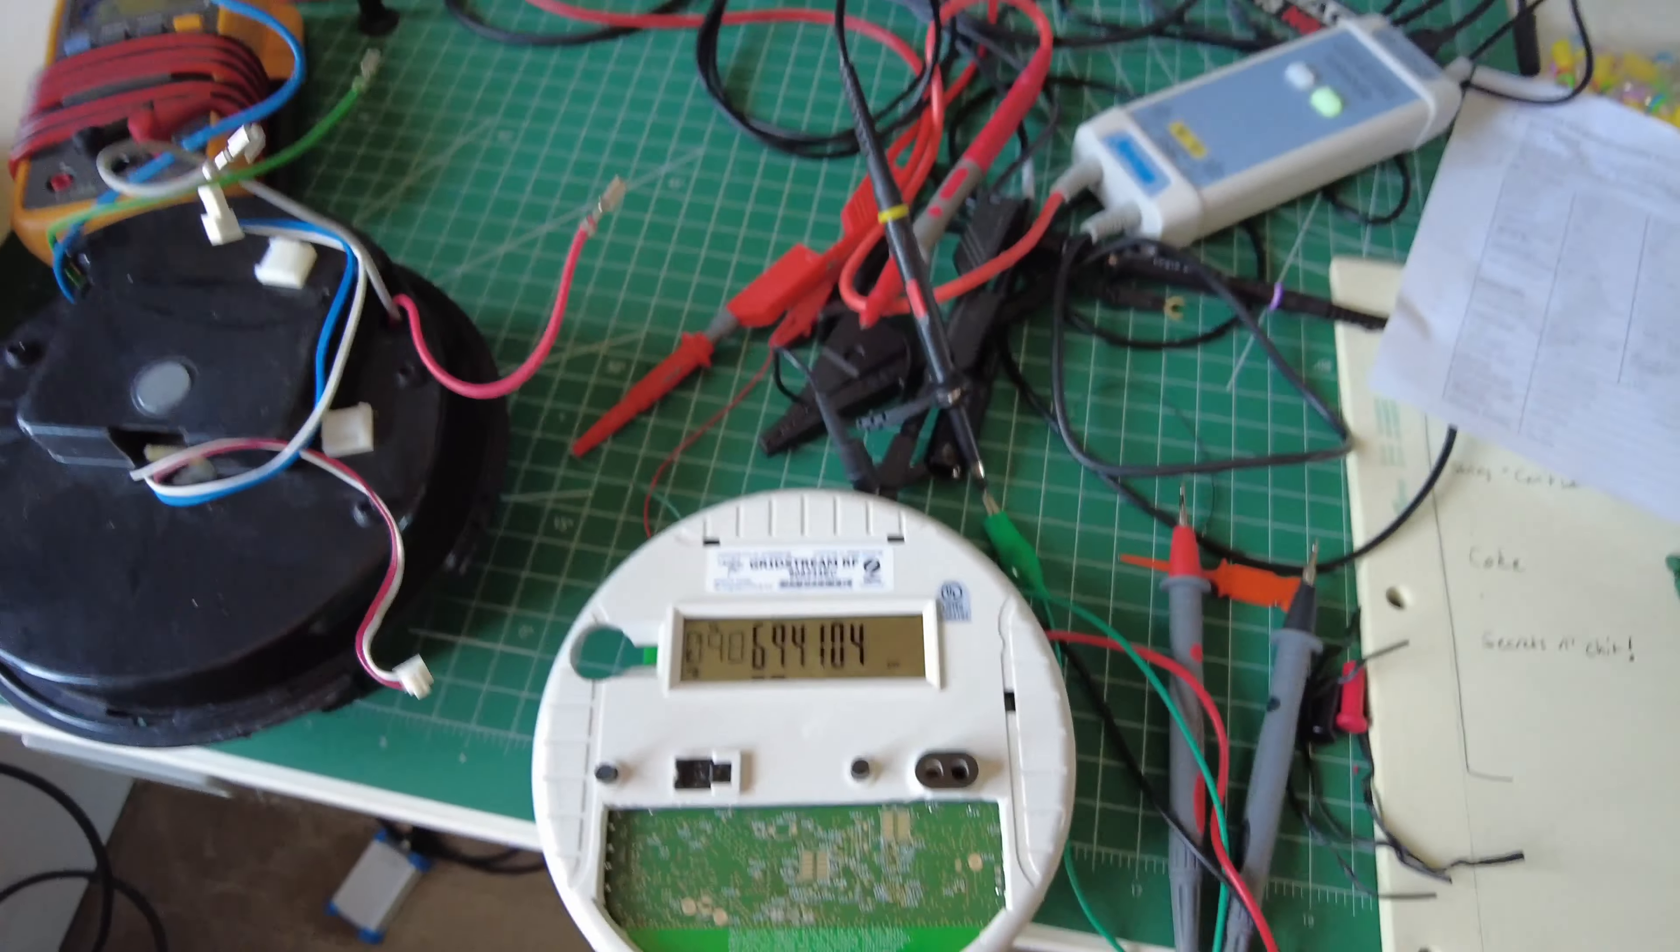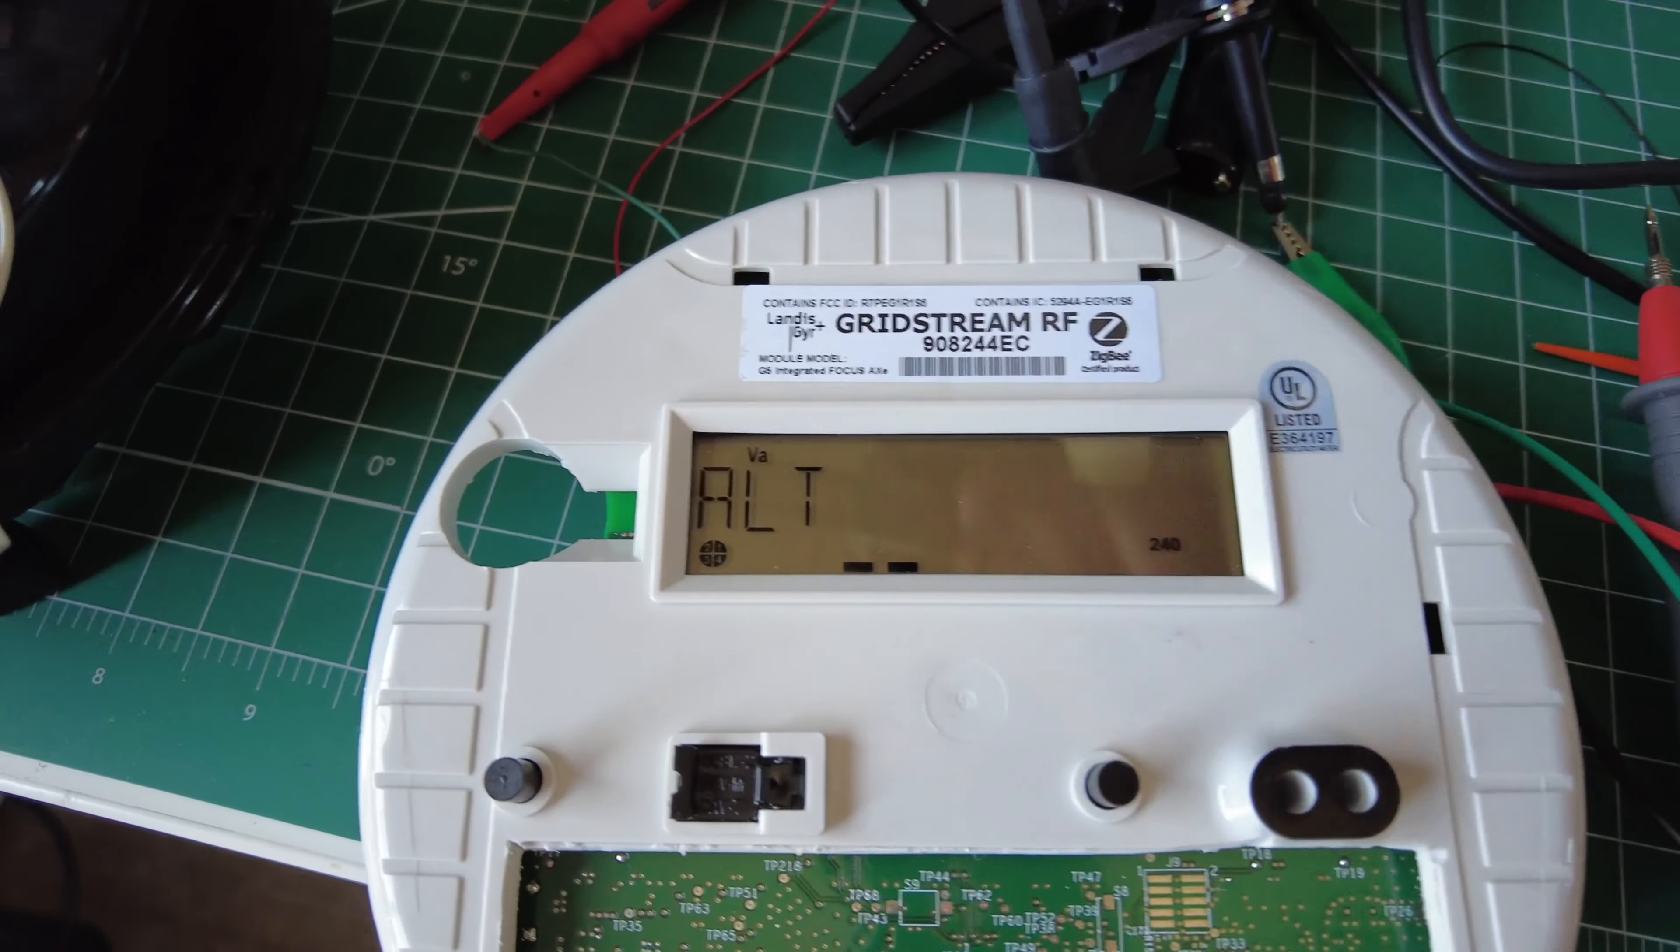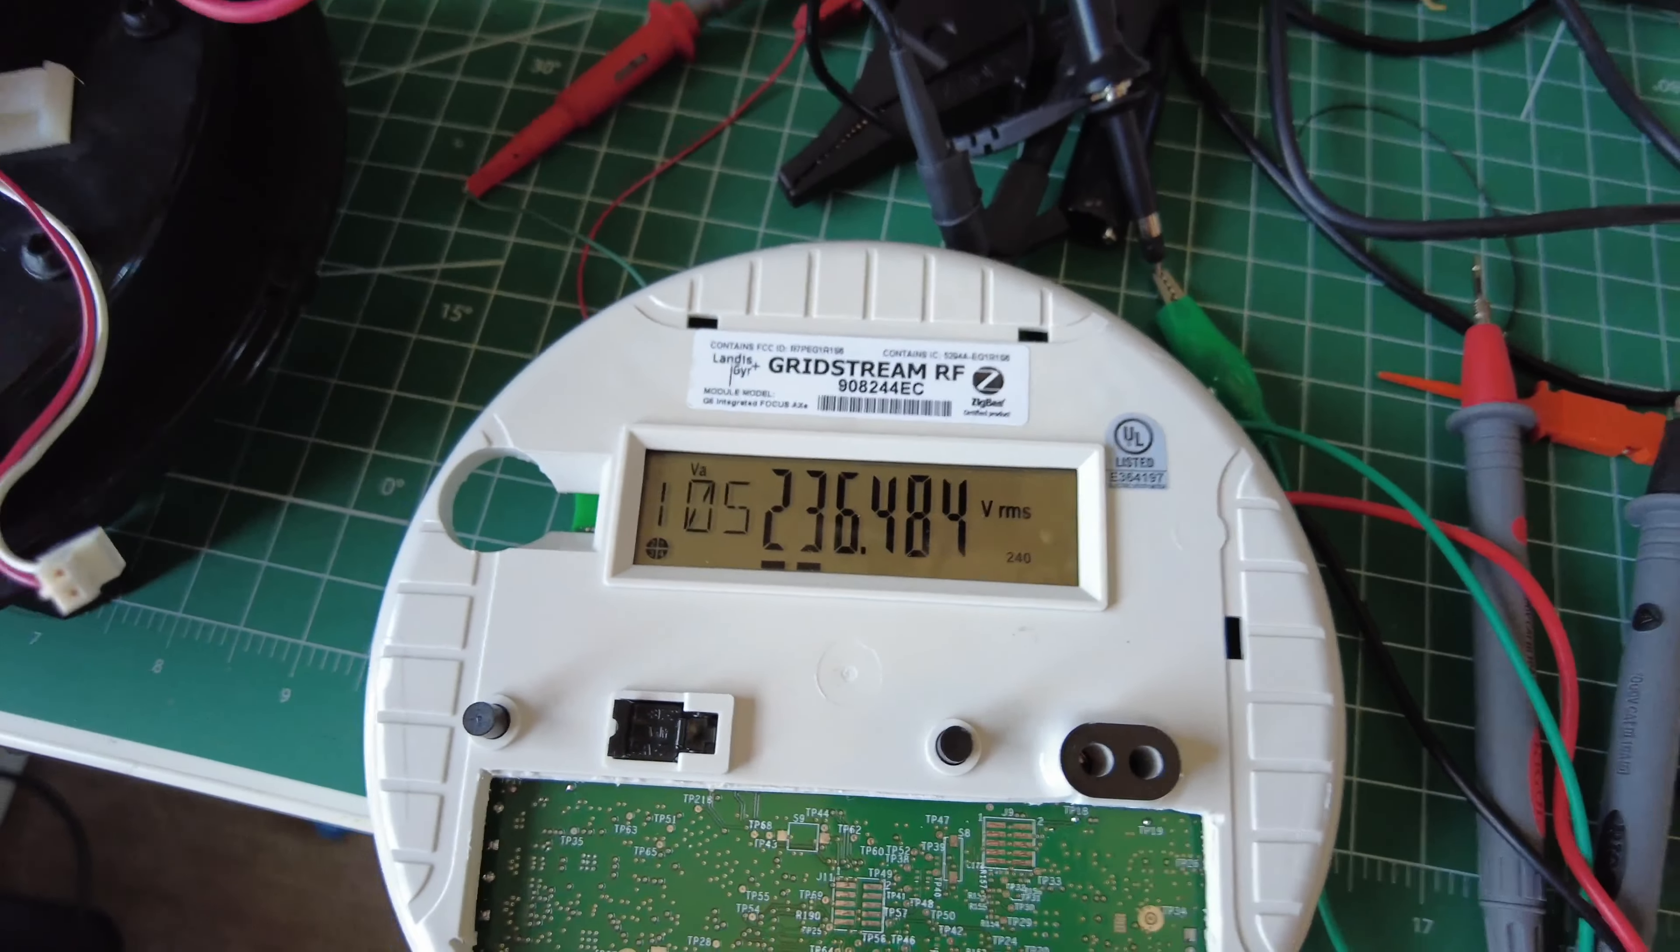And so if I put it into a little special test mode, okay, the screwdriver is magnetized, so up at the top of the meter here, if I put it right here, we'll see I go to this Alt mode, and I can cycle through some menu settings, and this 105 shows us what it thinks the line voltage is.